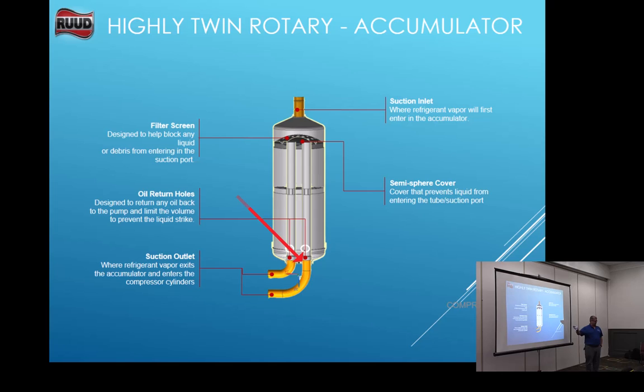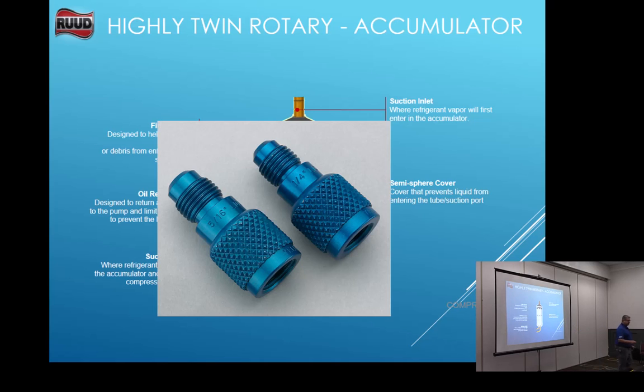I didn't show you all this earlier, but to keep liquid from getting into your systems, does everybody have a charge adapter for their hoses? Tim says he's got them in stock, so you need to get one. They're less than $10 probably, okay? But we're not supposed to ever, in any of the charging instructions, it says, you have 410A, you have to get it out of the drum as a liquid, but it says do not put liquid in the suction line. And for years, contractors say, well, how the hell can you do that, right?